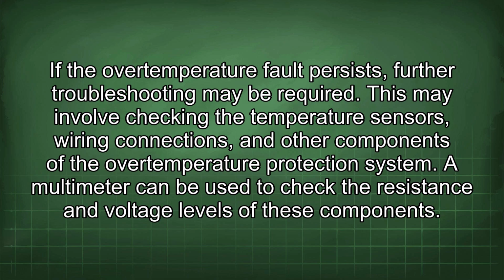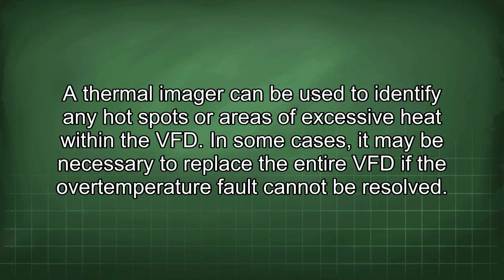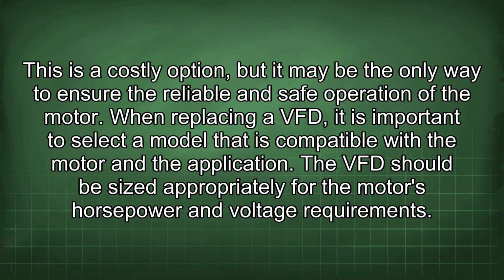This may involve checking the temperature sensors, wiring connections, and other components of the overtemperature protection system. A multimeter can be used to check the resistance and voltage levels of these components. A thermal imager can be used to identify any hot spots or areas of excessive heat within the VFD. In some cases, it may be necessary to replace the entire VFD if the overtemperature fault cannot be resolved.